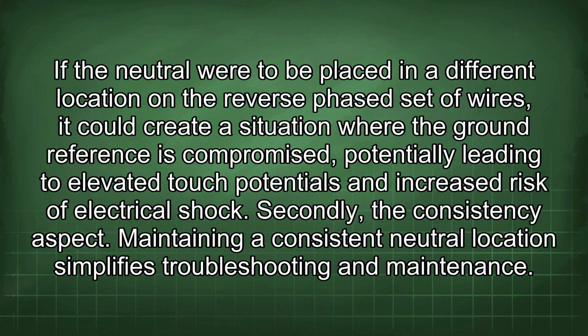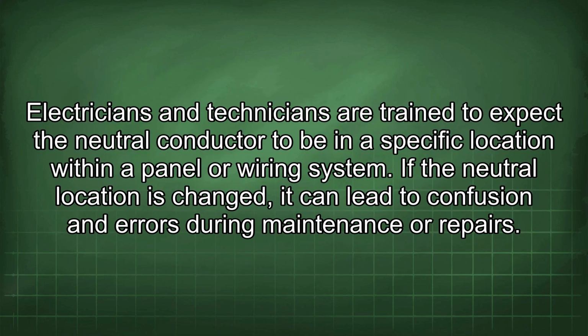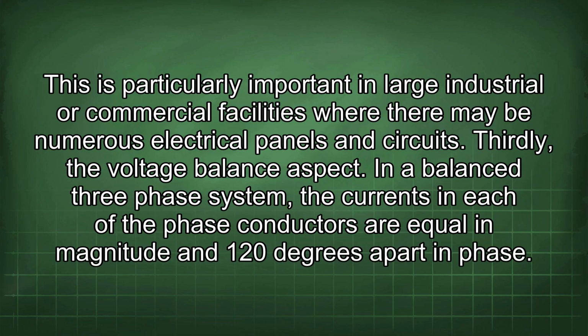Secondly, the consistency aspect. Maintaining a consistent neutral location simplifies troubleshooting and maintenance. The electricians and technicians are trained to expect the neutral conductor to be in a specific location within a panel or wiring system. If the neutral location is changed, it can lead to confusion and errors during maintenance or repairs. This is particularly important in large industrial or commercial facilities where there may be numerous electrical panels and circuits.